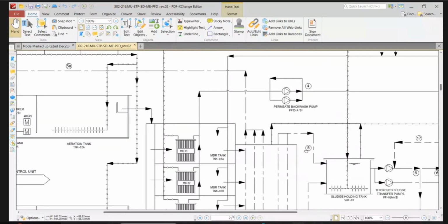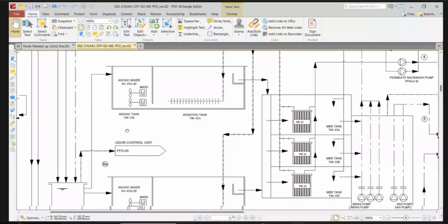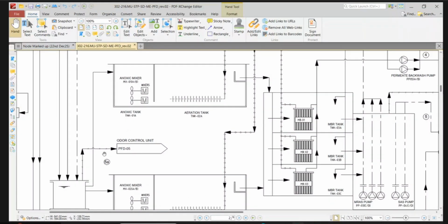That one is connected to the flow meters, and you have to take the reading from the inlet. It's based on the ratio. So, it will be like 3 times the inlet flow. You have to return it back. Yeah. And if the inlet flow is 100 cubic meter, you have to return 300 cubic meter. This is in the worst scenario. Sometimes 200. So this one depends on the operators.